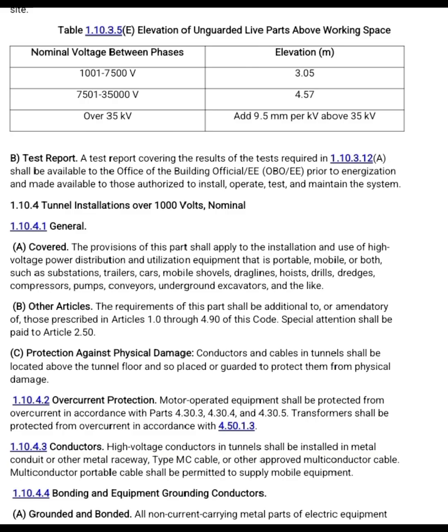1.10.4.2 Overcurrent protection. Motor-operated equipment shall be protected from overcurrent in accordance with Parts 4.30.3, 4.30.4 and 4.30.5. Transformers shall be protected from overcurrent in accordance with 4.50.1.3. 1.10.4.3 Conductors. High voltage conductors in tunnels shall be installed in metal conduit or other metal raceway. Type MC cable or other approved multi-conductor cable, or multi-conductor portable cable, shall be permitted to supply mobile equipment.